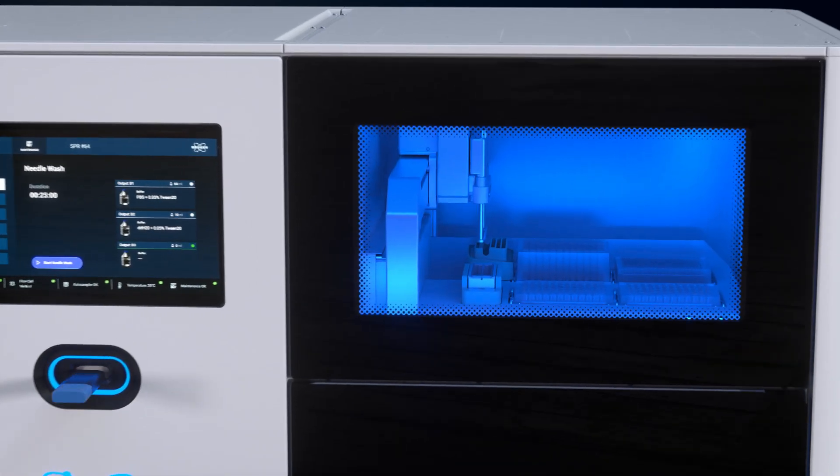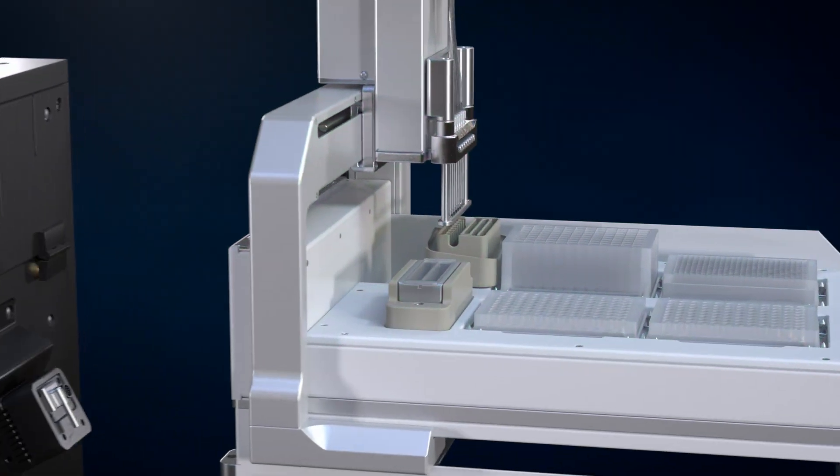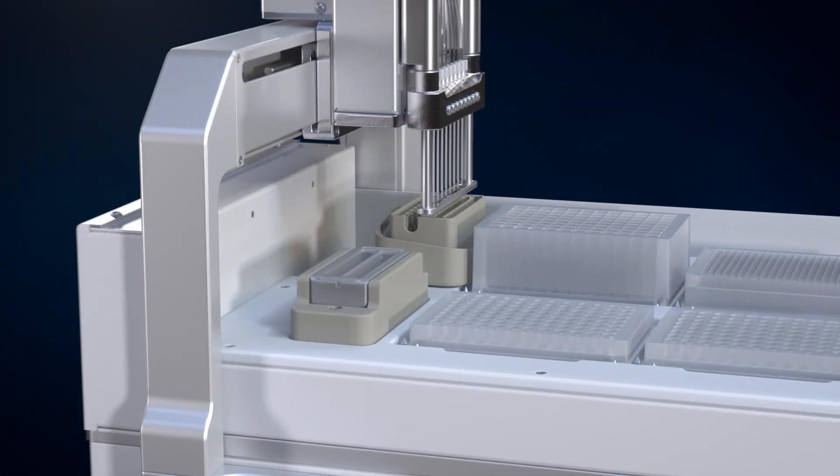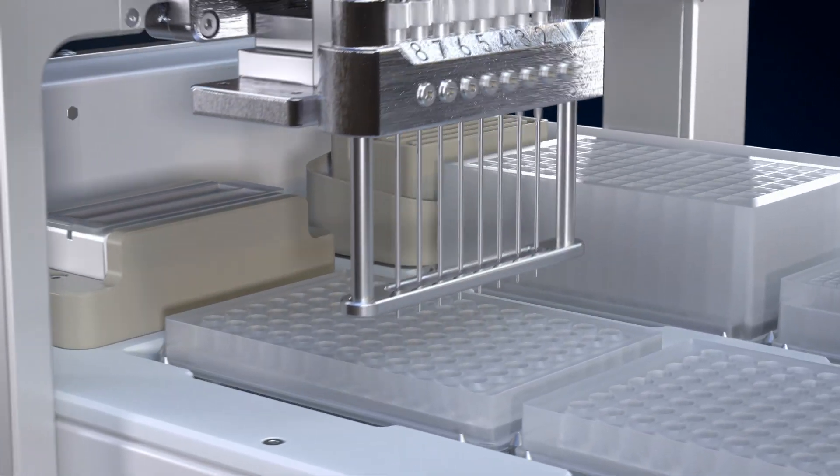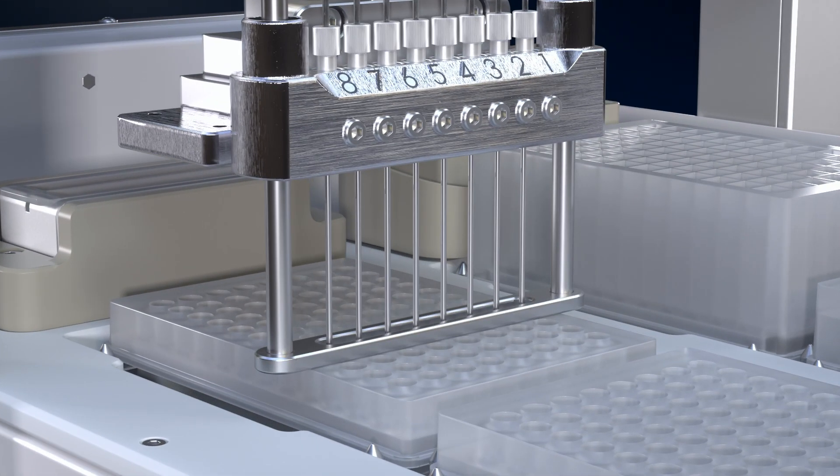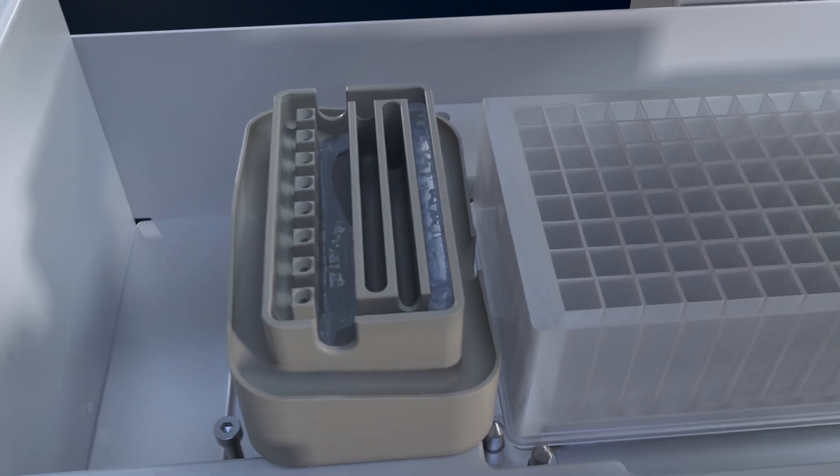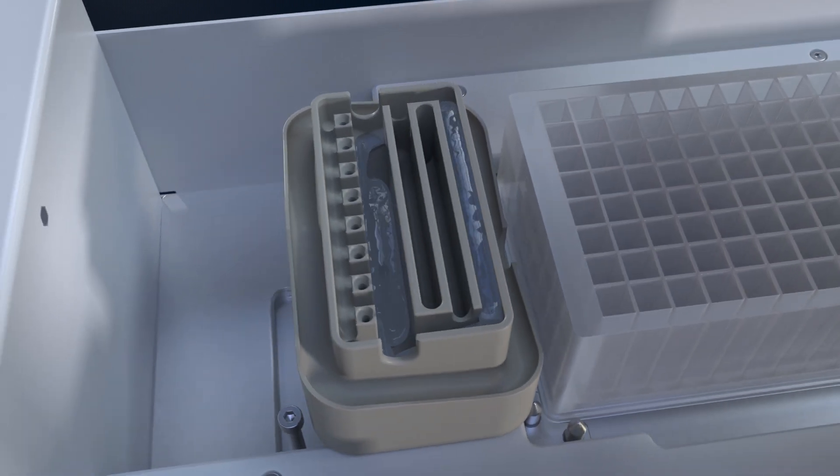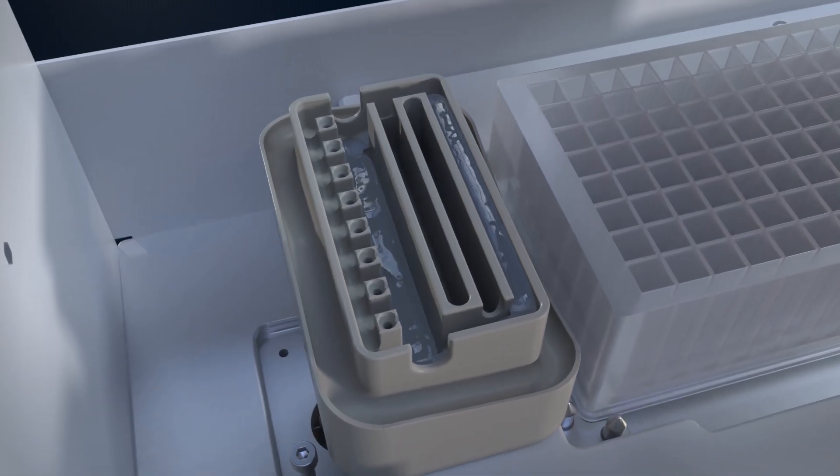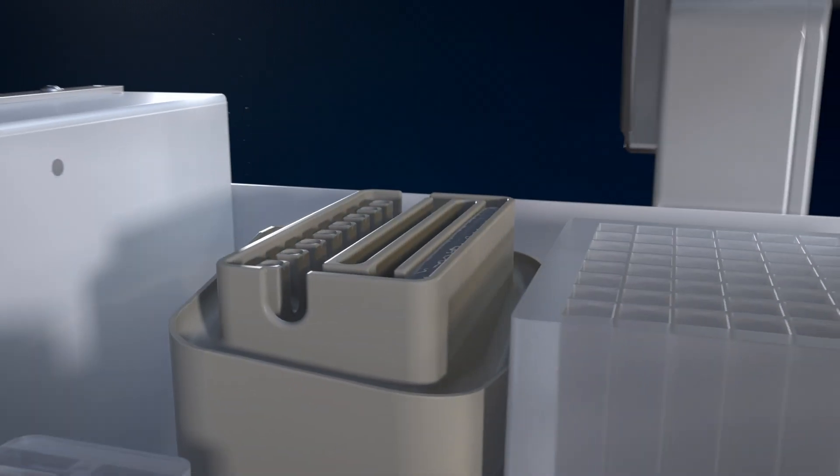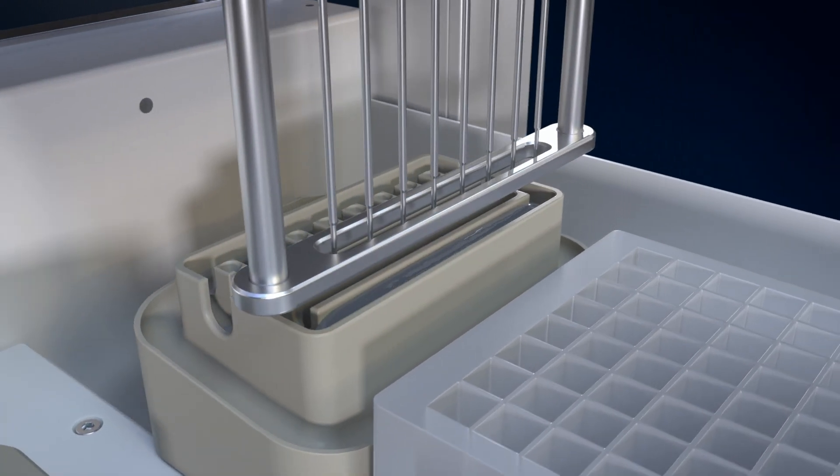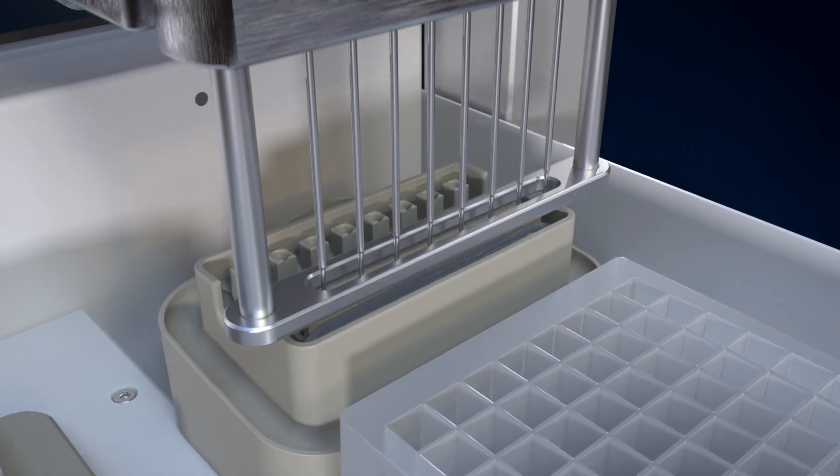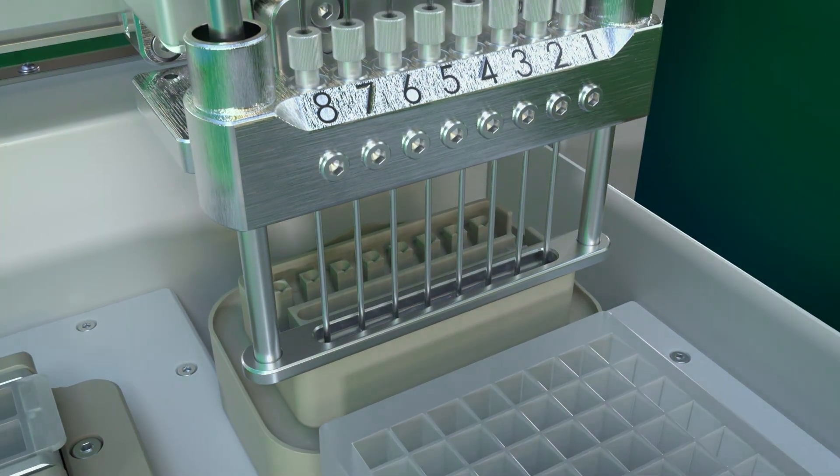The auto-sampler unit allows the usage of up to four microtiter plates, 96 or 384 well in parallel. If extended experiments are planned, the wash station offers two additional reagent pickup positions which can be directly connected to an external bottle.